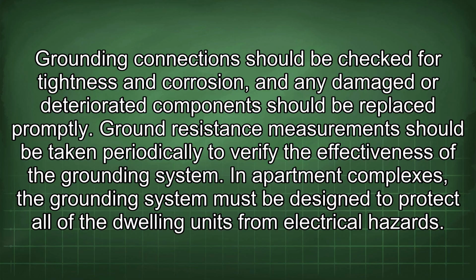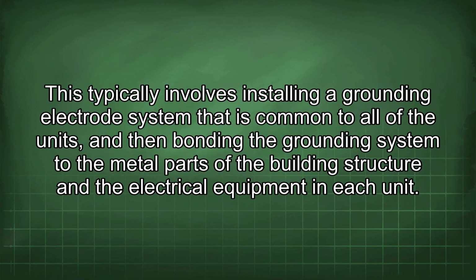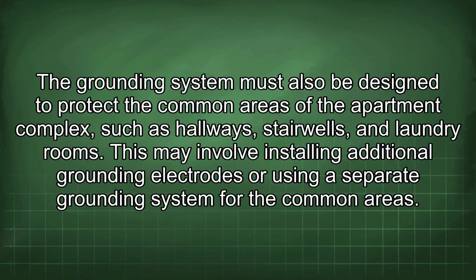In apartment complexes, the grounding system must be designed to protect all of the dwelling units from electrical hazards. This typically involves installing a grounding electrode system that is common to all of the units, and then bonding the grounding system to the metal parts of the building structure and the electrical equipment in each unit. The grounding system must also be designed to protect the common areas of the apartment complex, such as hallways, stairwells, and laundry rooms. This may involve installing additional grounding electrodes or using a separate grounding system for the common areas.